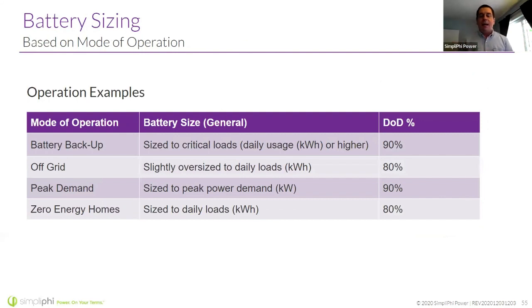Well, what installations might be applicable for such use? If you're using battery backup, maybe a couple dozen outages a year, a couple dozen cycles via an outage, 100% depth of discharge may be appropriate. We'd like to say 90%, which gives you that little 10% left over, just to make sure the battery has enough to kick back on after the outage. If you're off grid and you're cycling that battery every day, 80% is appropriate. And it's going to benefit you too, because you'll have additional capacity after the warranty period.